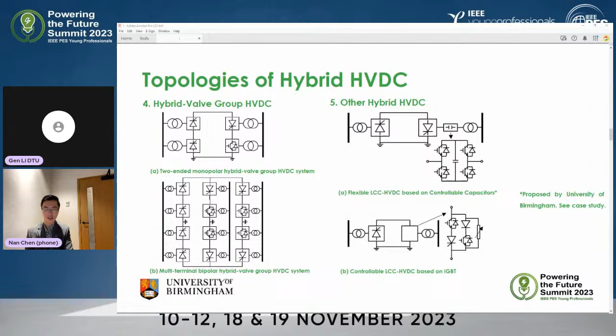So next, I will introduce several best applications of hybrid HVDC, which have been realized and installed all over the world. The first one will be the hybrid infeed HVDC. One of the typical applications is the Luxi back-to-back HVDC project. I have put some references here. If you are interested, you can look into more details. It consists of two LCC HVDC, 1 gigawatt each at the voltage level of 160 kV, and also one VSC HVDC with the transferring capacity of 1 gigawatt at the voltage level of 350 kV.